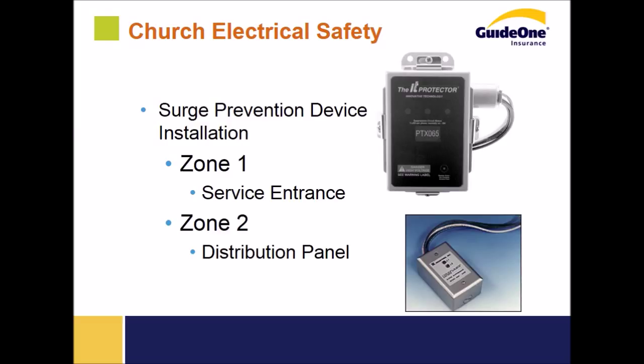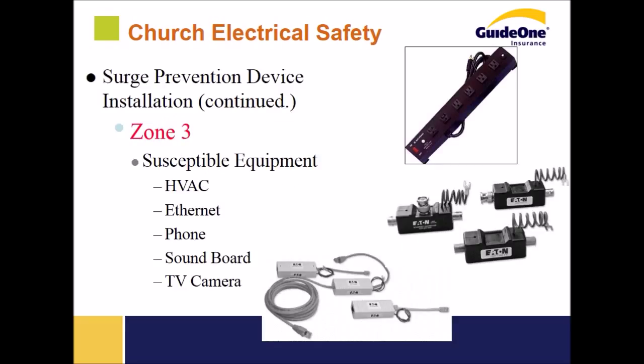With surge protection, it's a zoned approach. You install zone 1 protection at the service entrance, zone 2 protection at any distribution panel present, and zone 3 at the point of use—power strips for computers, surge devices for data lines, Ethernet, phone systems, soundboards, TV cameras, and so on. It's important that surge protection be in place across all 3 zones. We need you to report when this equipment is present, and if you see evidence of damage or concern, we'd like a recommendation made as well.